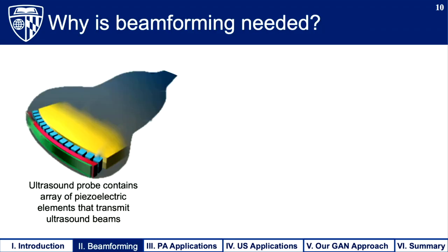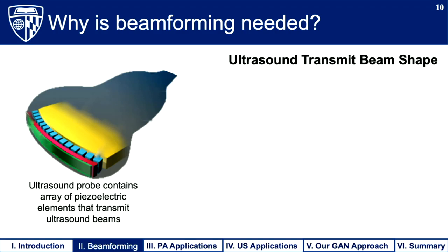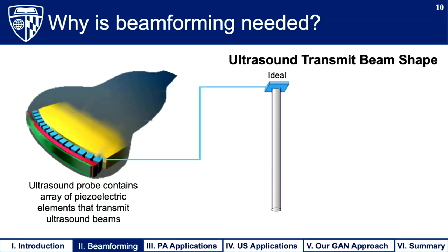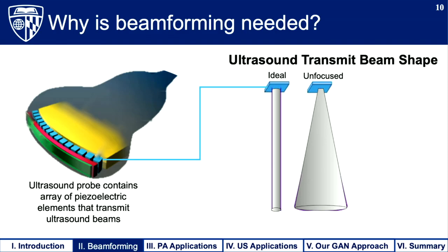Why exactly is beamforming needed? The probe contains an array of piezoelectric elements used to transmit mechanical pressure waves into the body. Ideally we want the transmitted beam to be infinitely narrow as depth increases, but due to the physics of wave propagation we instead get a beam that starts off narrow and then widens as depth increases. Beamforming is our attempt to give us something that looks more like the ideal beam shape at a specific focal depth.